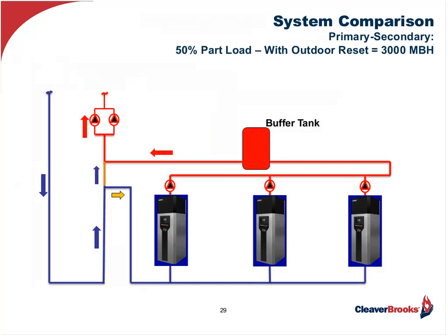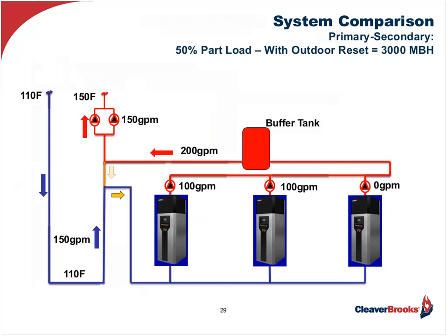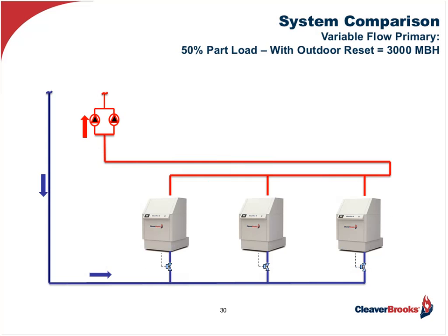Now let's look at 50% load with outdoor air reset. In this case, we have 150 degrees going out with 110 coming back. We've reset that temperature down because we're not at full load. That gives us about 150 GPM on the system. In this case, we're only going to run 2 boilers, which will give us 200 GPM and 50 GPM in the decoupler coming back. So again, we're going to get mixing. The boilers aren't going to see the 110 degrees, they're going to see 120. The two boilers running will operate at a 75% firing rate to make up that load. One boiler is off.